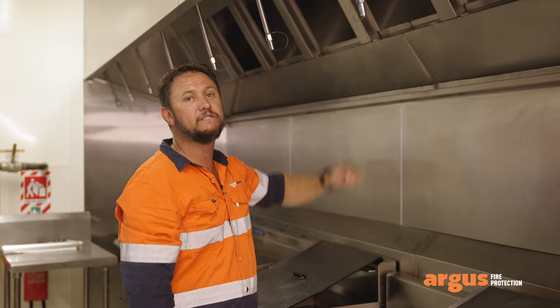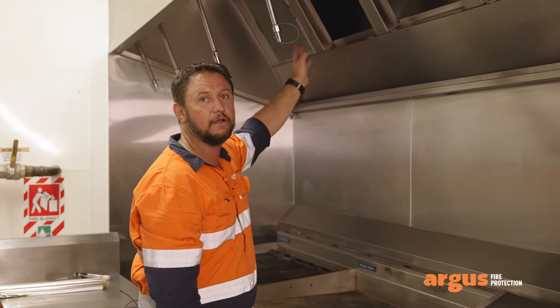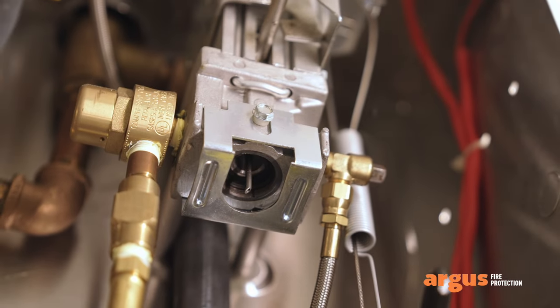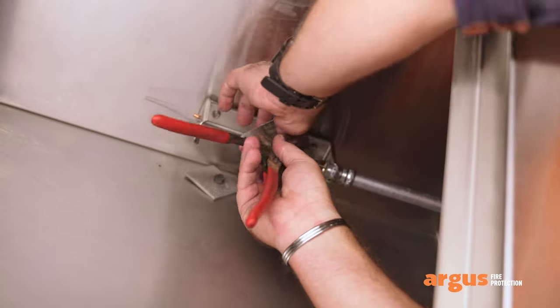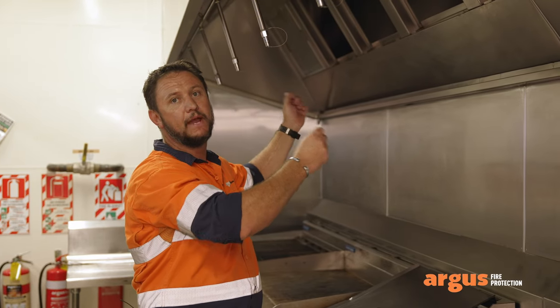We then move under the hood and up into the plenum. What we're looking for is our automatic detection system. We test the system by cutting the thermal link — when that happens it should activate the system. Once that's happened, we change all the links out with new ones and reinstate the automatic detection system back into its normal state.